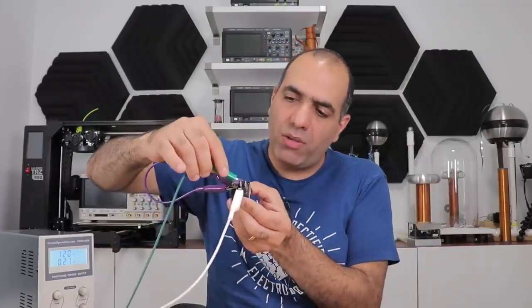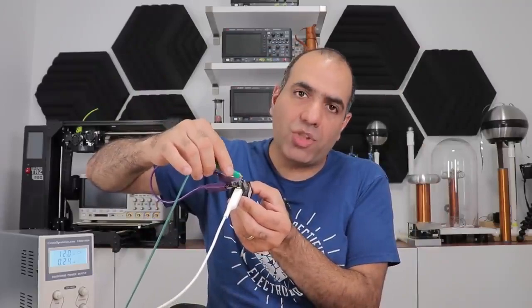So if the high voltage and power is available between your contacts, the arcs may never go away and keep your contacts shorted or open after a long time, which can melt your contacts and damage your relay and short your circuits. Such high voltages can happen when you switch inductive loads, like I showed. So you must keep the switching voltage and current below the relay rating for reliable switching. Fun! But that's not all.